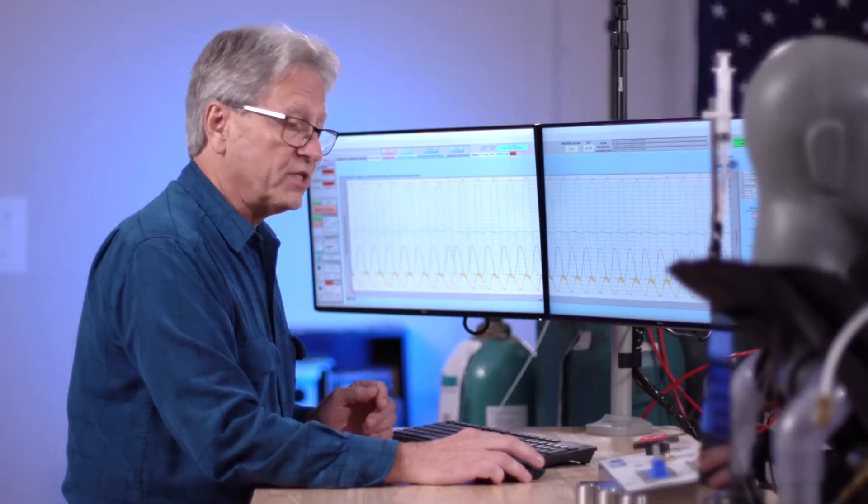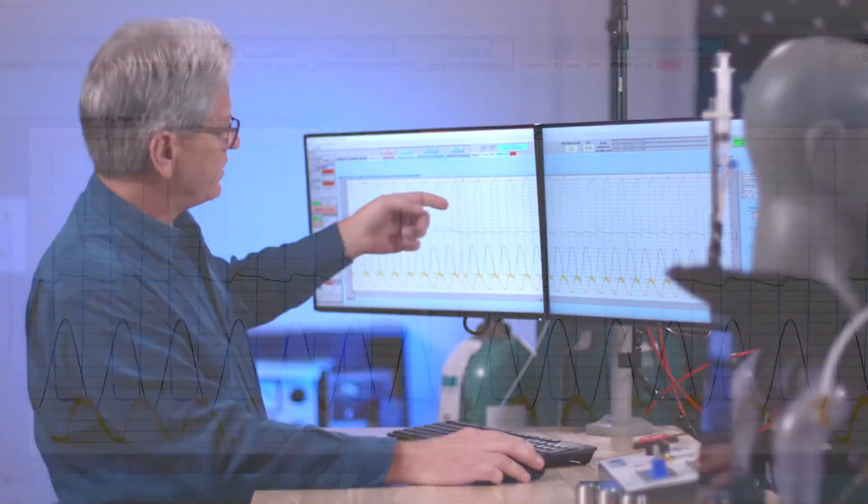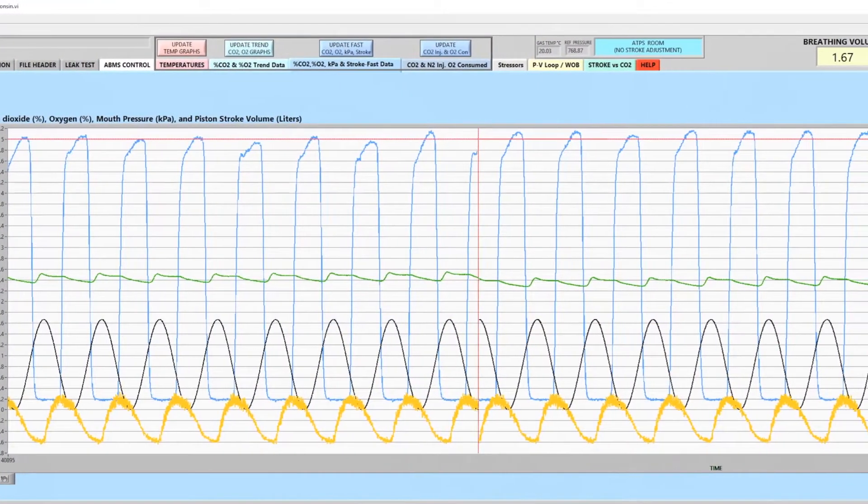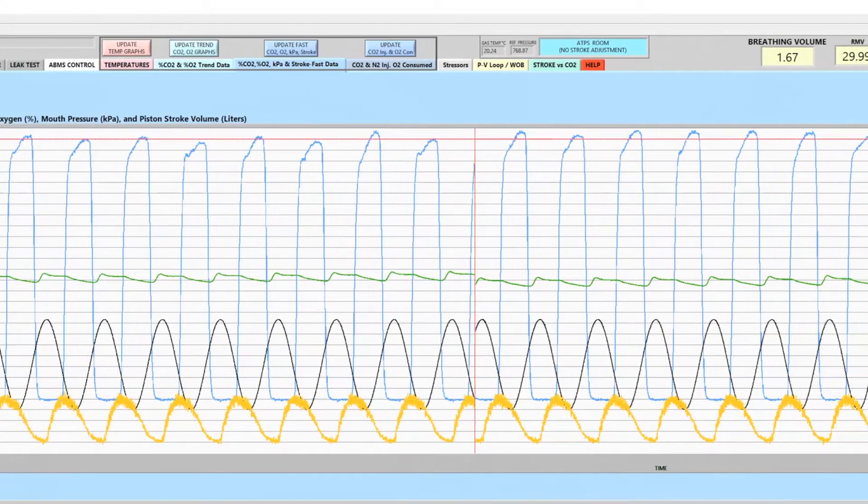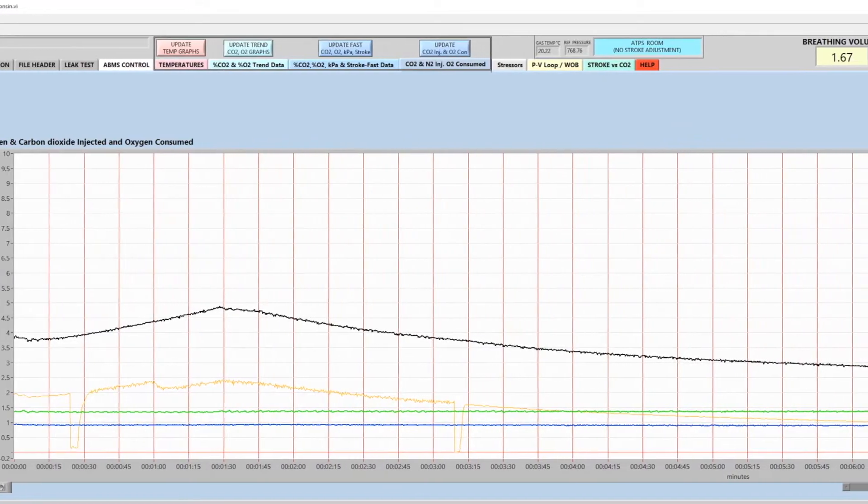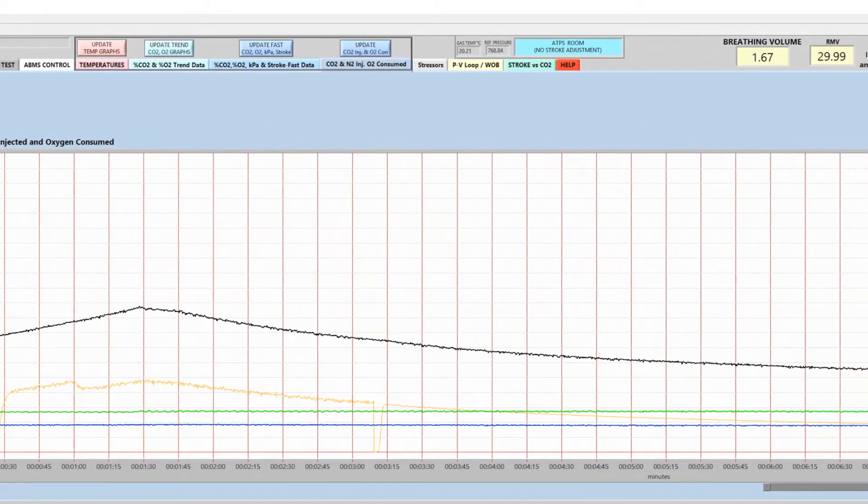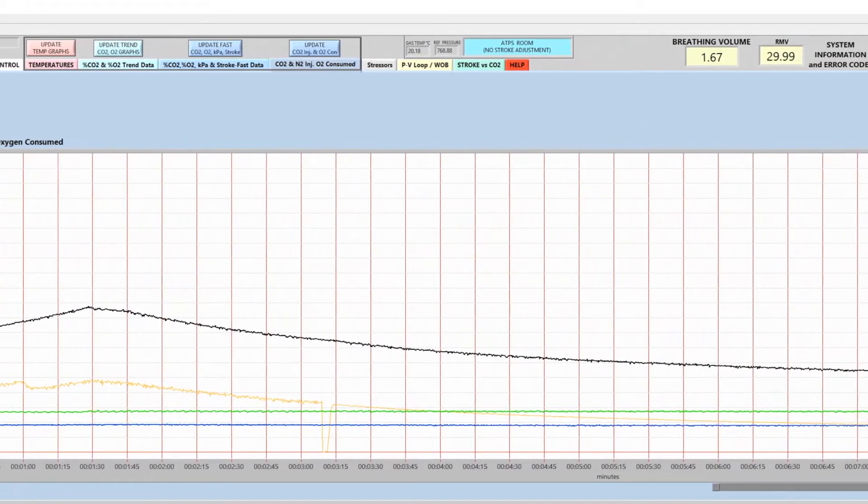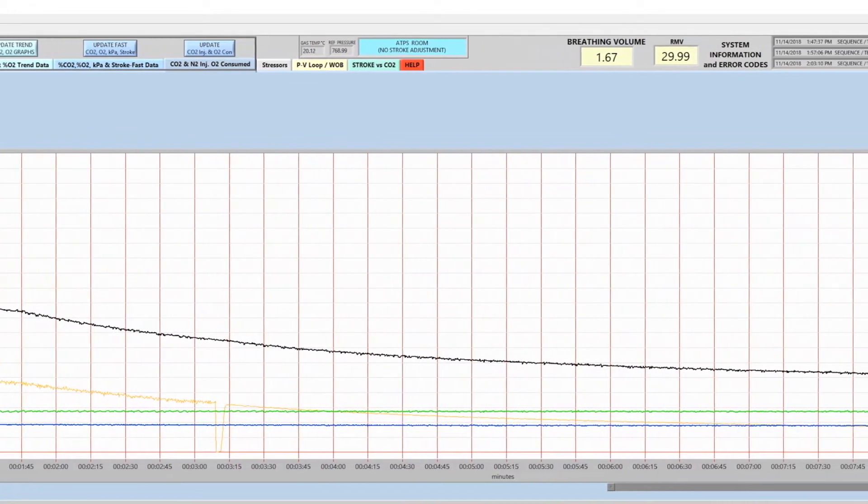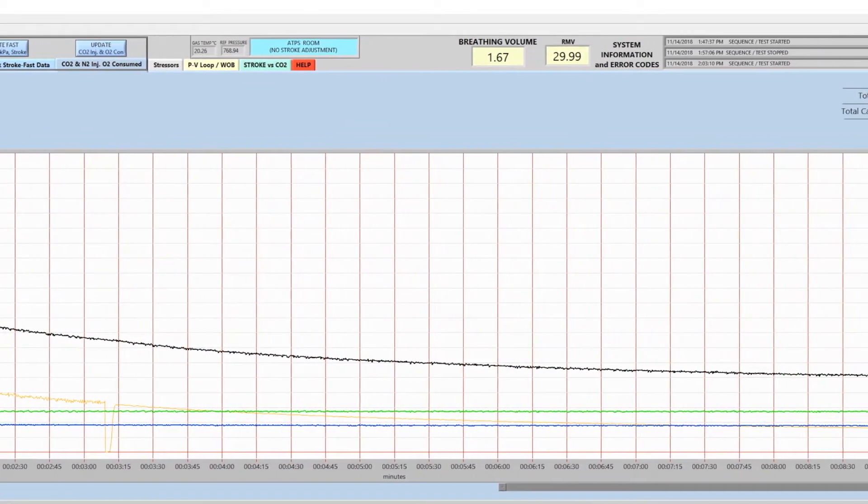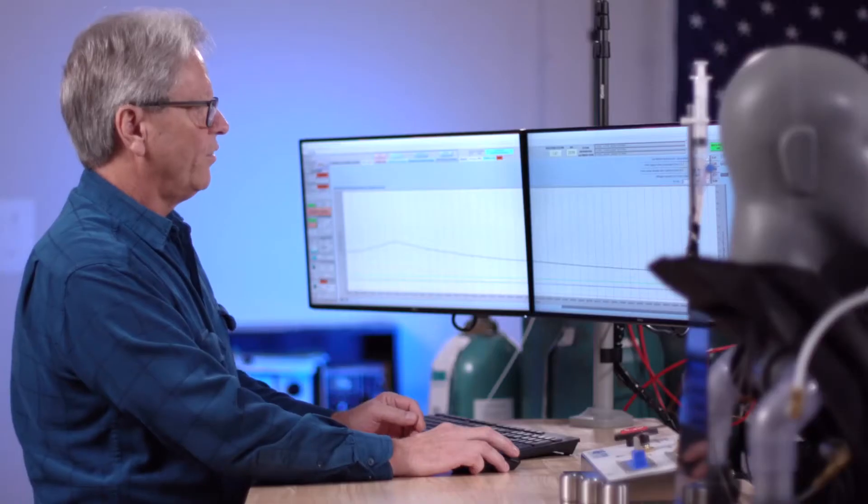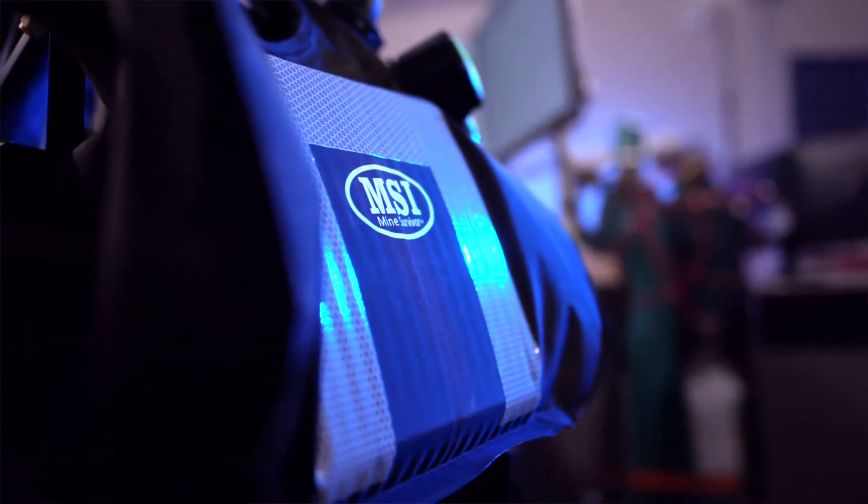On this data screen, as previously described, we see the carbon dioxide and oxygen as they cycle through the breathing process. As the gas mixture coming from the apparatus stabilizes, we see that the amount withdrawn and the amount re-injected stabilize as the oxygen content starts to increase. These processes are followed in order to determine how long an apparatus will continue to remove the carbon dioxide and provide the oxygen that the user requires.